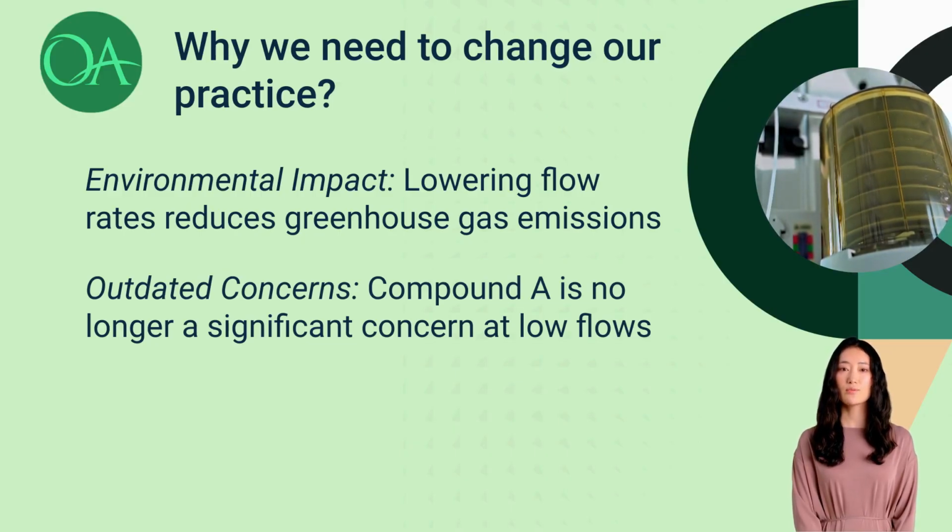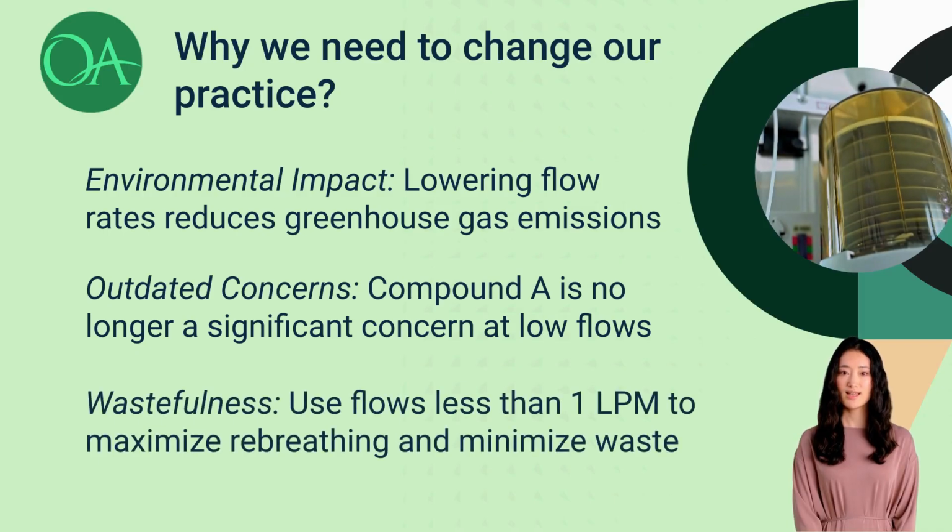Additionally, using 2 liters per minute is wasteful. Instead, we should use flow rates below 1 liter per minute to maximize rebreathing and minimize waste, enhancing both sustainability and efficiency in our anesthesia practices.